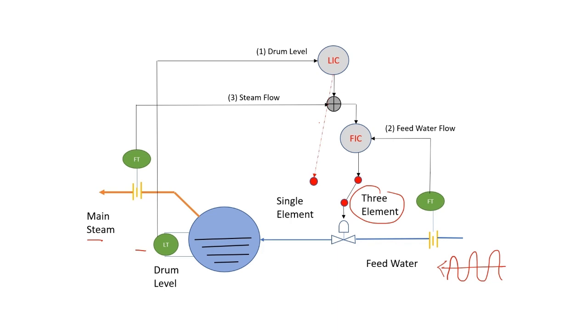In that case, there is a switching option that operator can select or that can be done automatically through logic. In that case, LIC directly sends the signal to the feed water control valve, and in this way the level of the boiler is maintained.